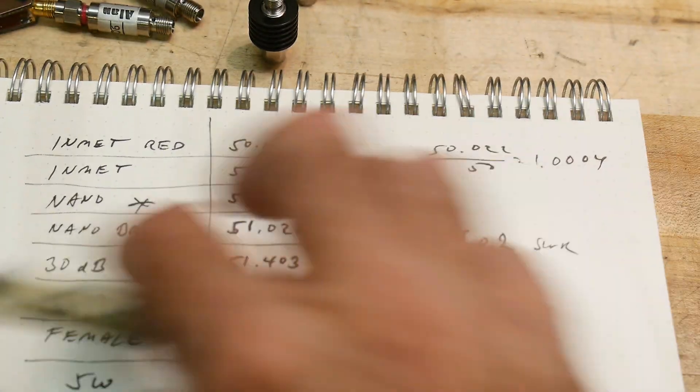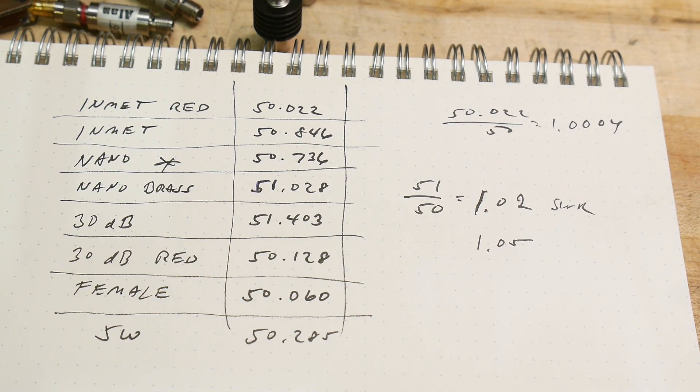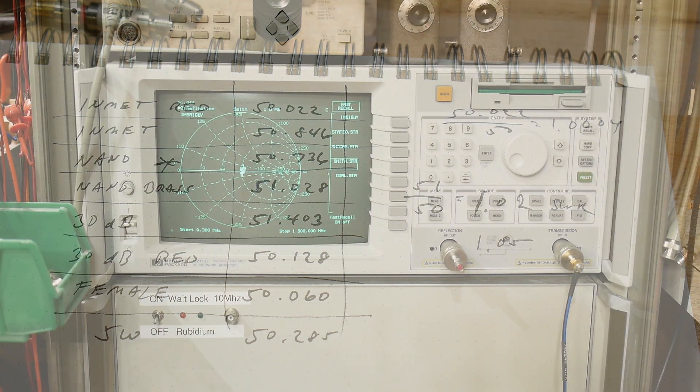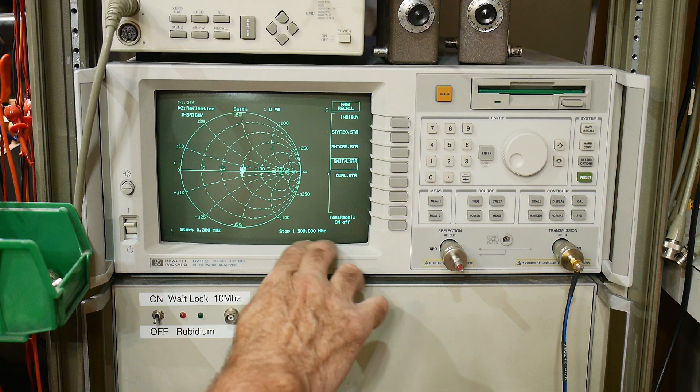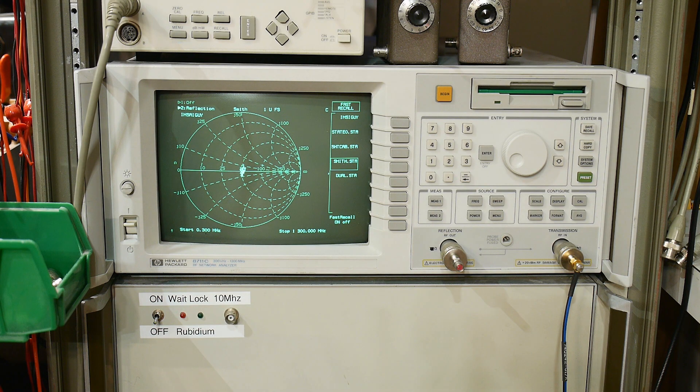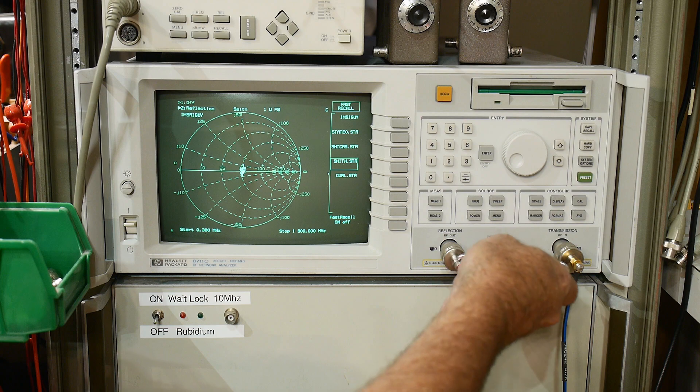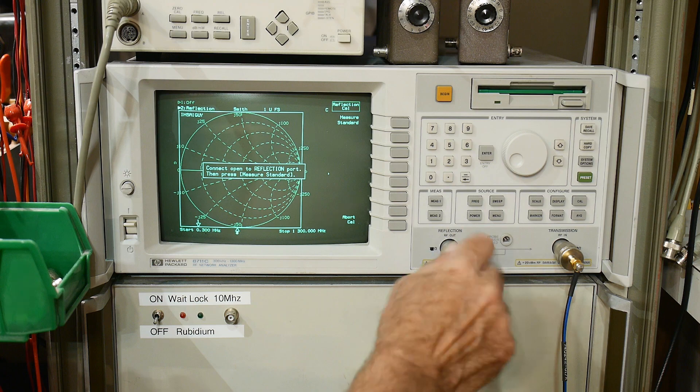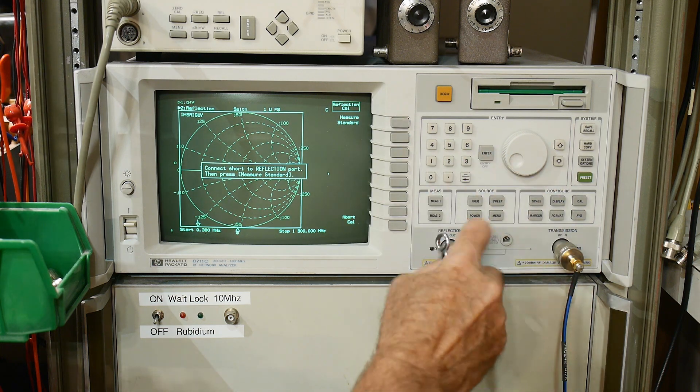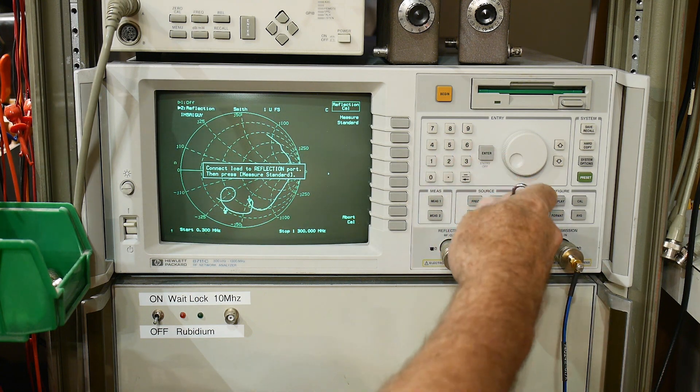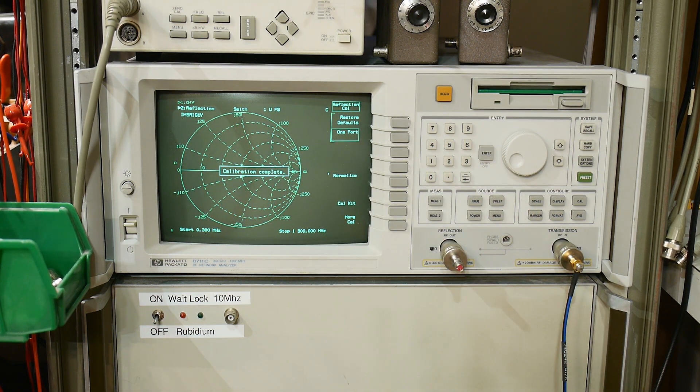So now that we kind of have these things in a DC mode, right? DC, a DC calibration, let's go over to the VNA and take a look at them. So we're going to be sweeping between 0.3 megahertz and 1300 megahertz, 1.3 gigahertz. So let's go ahead and we'll do a fresh cal. Calibration complete.